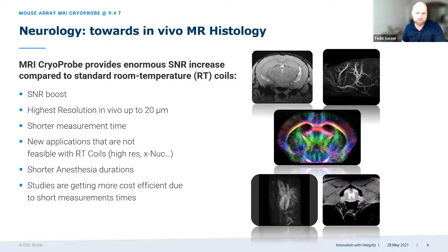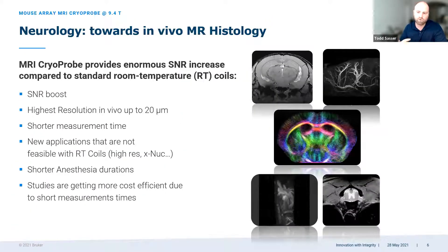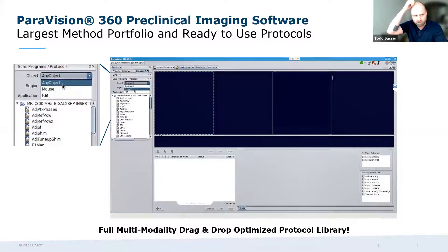You have a cryo coil or cryoprobe, which is a completely unique piece of hardware. Unlike a room temperature coil, it is deeply cooled with a cryogen, which allows you to boost your sensitivity. Combined with the 9.4 T magnet and the cryo coil, you get roughly the equivalent of a 12 Tesla signal-to-noise ratio — really at the very edge of what can be done.